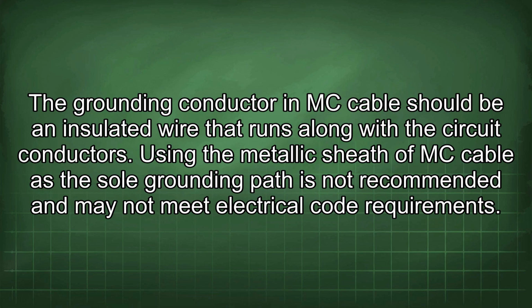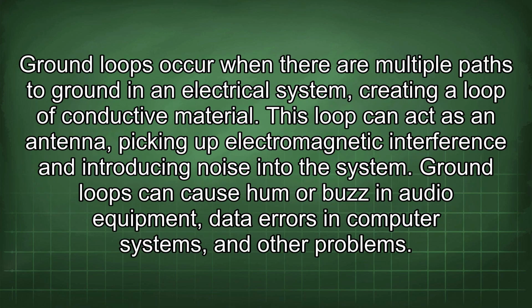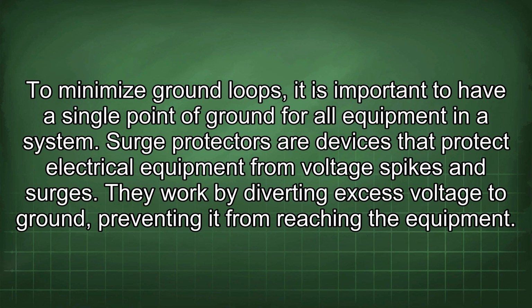Ground loops occur when there are multiple paths to ground in an electrical system, creating a loop of conductive material. This loop can act as an antenna, picking up electromagnetic interference and introducing noise into the system. Ground loops can cause hum or buzz in audio equipment, data errors in computer systems, and other problems. To minimize ground loops, it is important to have a single point of ground for all equipment in a system.